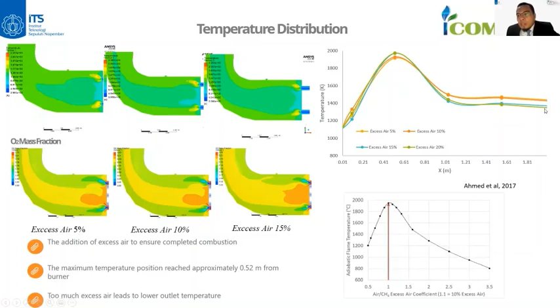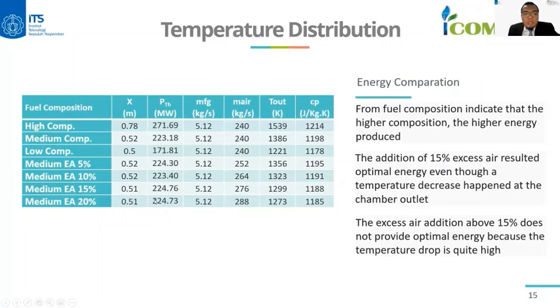Now about the energy comparison. From the three fuel gas compositions and the variation of excess air, we can say that from the fuel composition, the higher the composition, the higher the energy produced. Then the addition of 15% excess air results in optimal energy, although a temperature decrease happens at the chamber outlet. Then excess air addition above 15% does not provide optimal energy because the temperature drop is quite high.